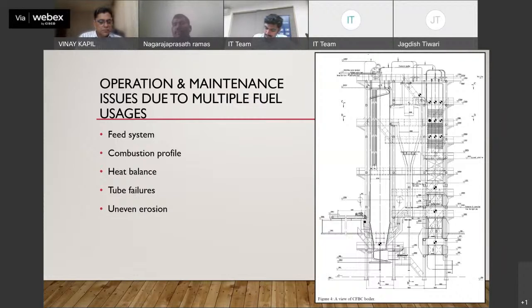Sometimes the cyclone gets choked due to the biomass bulk density. When the bulk density is low, there is an issue in the cyclone flowability, and the collected ashes do not flow back properly to the furnace. Once or twice we faced the cyclone choking problem whenever we fired husk more than 70%. Then we discussed and added a cyclone purging arrangement like air blasters, which people use in AFBC boilers. We provided the air blasters in the cyclone cone area. Afterwards it came down, but choking still happened once or twice.